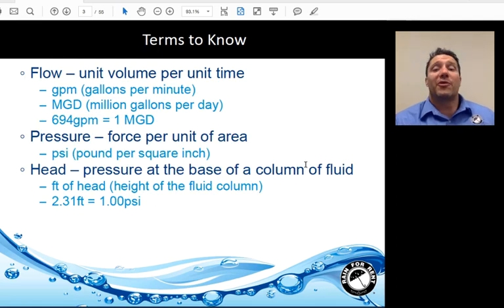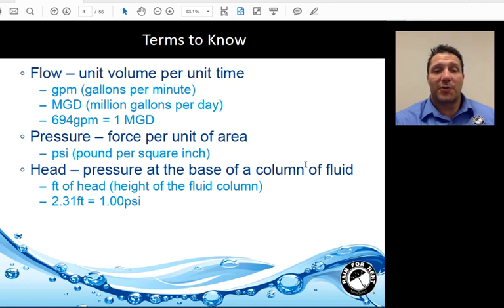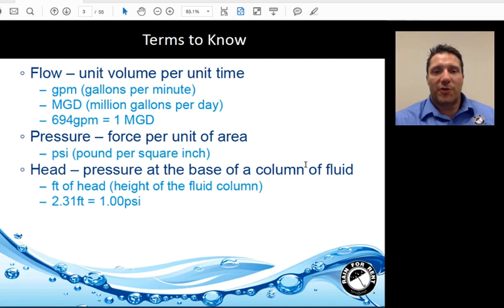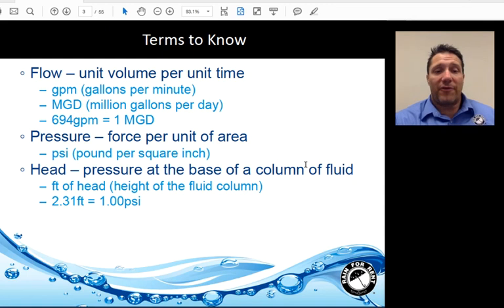Flow — unit of volume per unit of time — is probably the most important item when designing a bypass. Typically it's measured in gallons per minute or MGD, million gallons per day. One MGD is the equivalent of 694 gallons per minute. Pressure, force per unit of area, is typically measured in PSI. Head pressure, or simply head, is the pressure at the base of a column of fluid. It's typically measured in feet of water, and 2.31 feet is equivalent to 1 PSI.